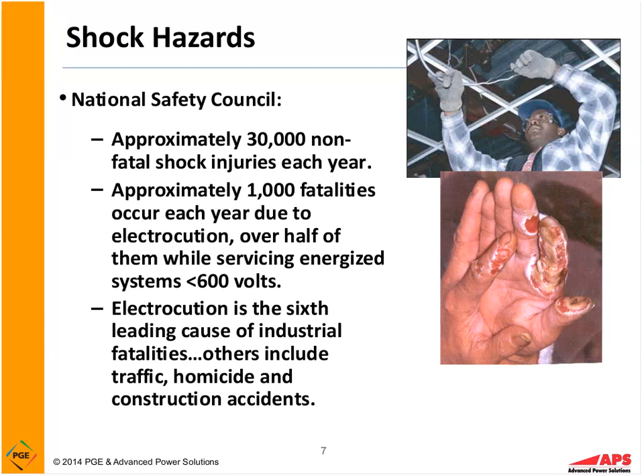Now, in the upper right-hand corner, the picture shows a gentleman working on a circuit for lighting. Hopefully that's de-energized, but a lot of people actually get hurt or injured or even killed working on lighting circuits, because it's a pretty common thing that people will go up and work on a ceiling on lighting circuits. And that shouldn't be common. There's no justification for working on a lighting circuit energized.